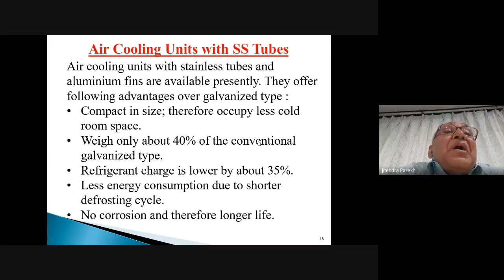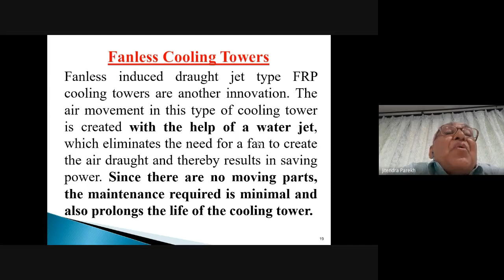Then again, fanless cooling towers, which are induced draft jet type FRP cooling towers, are another innovation. The air movement in this type of cooling tower is created with the help of a water jet, which eliminates the need for a fan to create the air draft, thereby saving power. There are no moving parts, the maintenance required is minimal, and it also prolongs the life of the cooling tower. So we recommend that we should have fanless type cooling towers. Next, please.